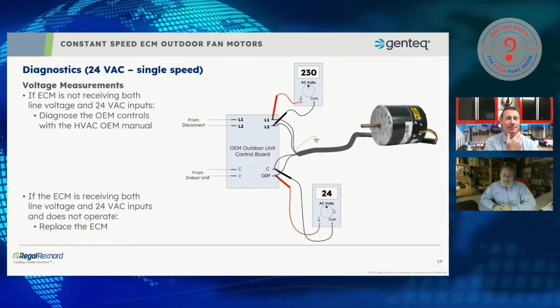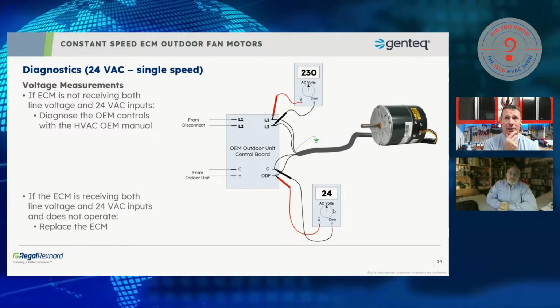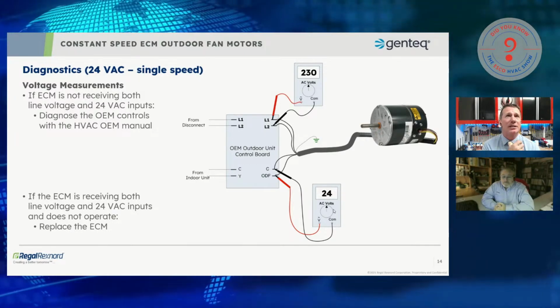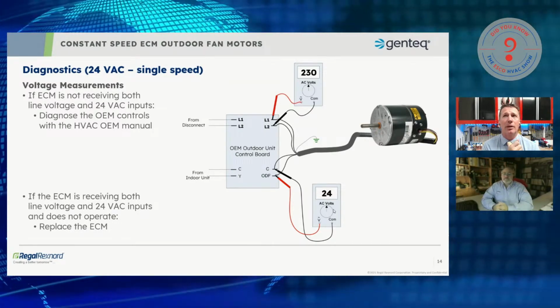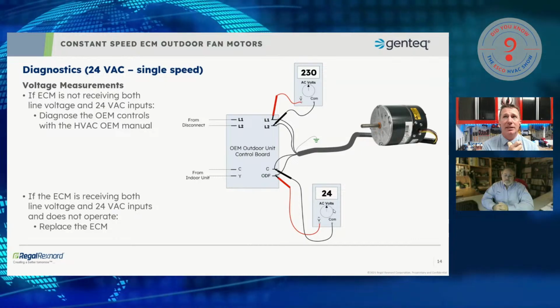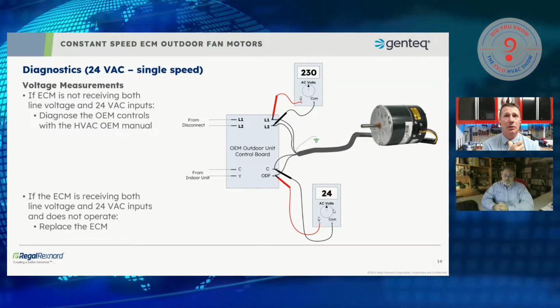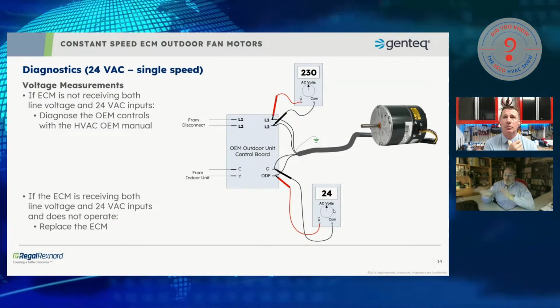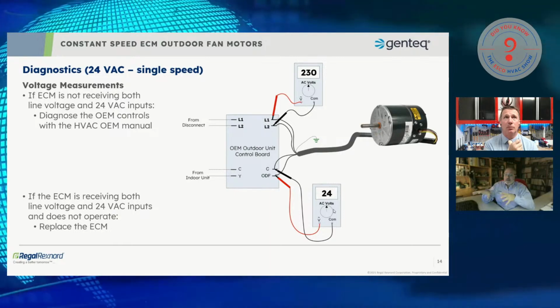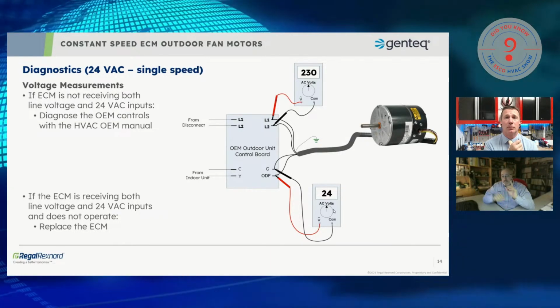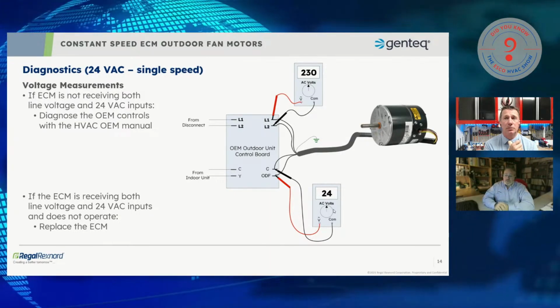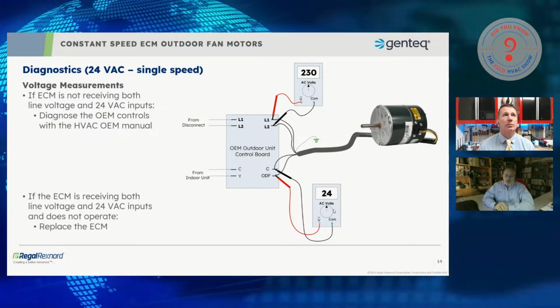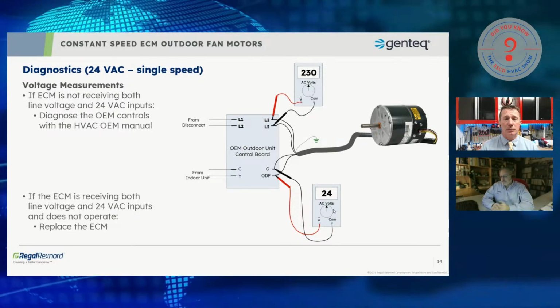Go ahead. No, in the same way, when I see what's out in the field and I see replacement motors, all that I'm seeing are complete motor assemblies. I've yet to see a separated motor. Yep. So again, before we change slides, if I have both inputs to the motor, in this case a single speed motor, so I have 24 volts going to the single speed, if the motor's not running, the motor's failed.